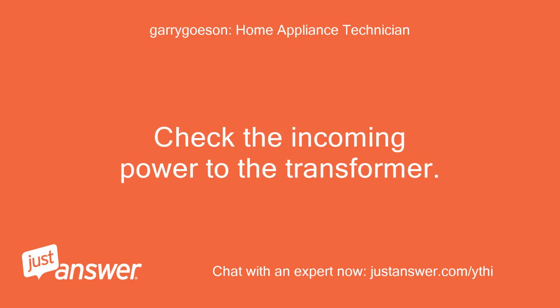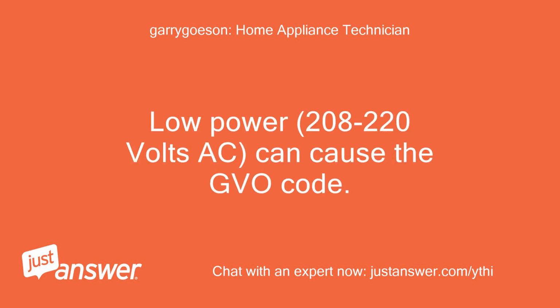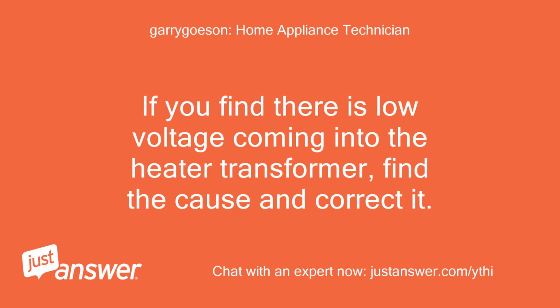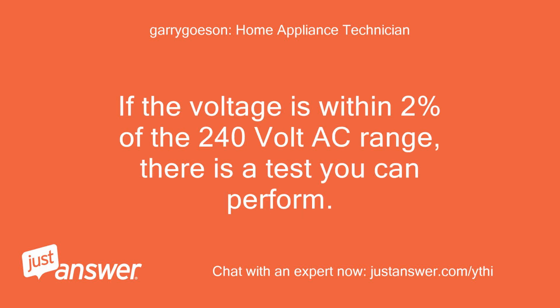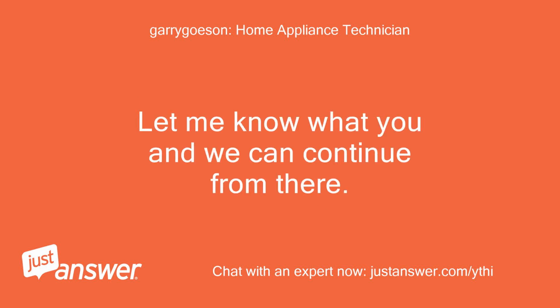Check the incoming power to the transformer. Low power, 208 to 220 volts AC, can cause the GV0 code. If you find there is low voltage coming into the heater transformer, find the cause and correct it. If the voltage is within 2% of the 240 volt AC range, there is a test you can perform. Let me know what you find and we can continue from there. Thank you.